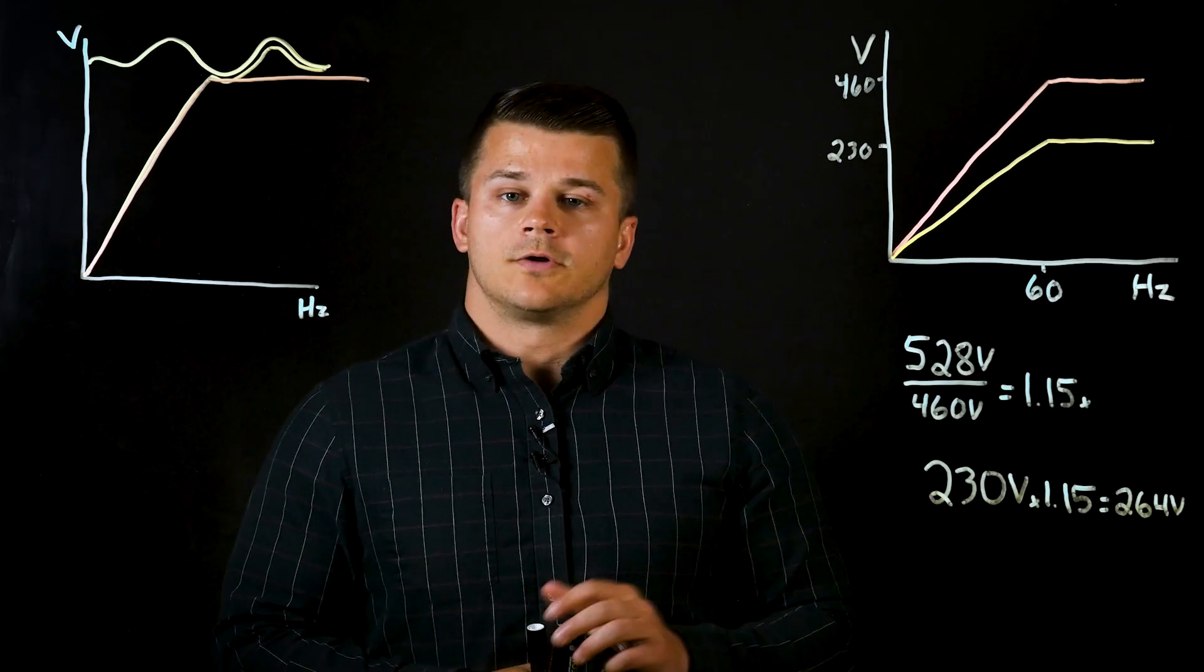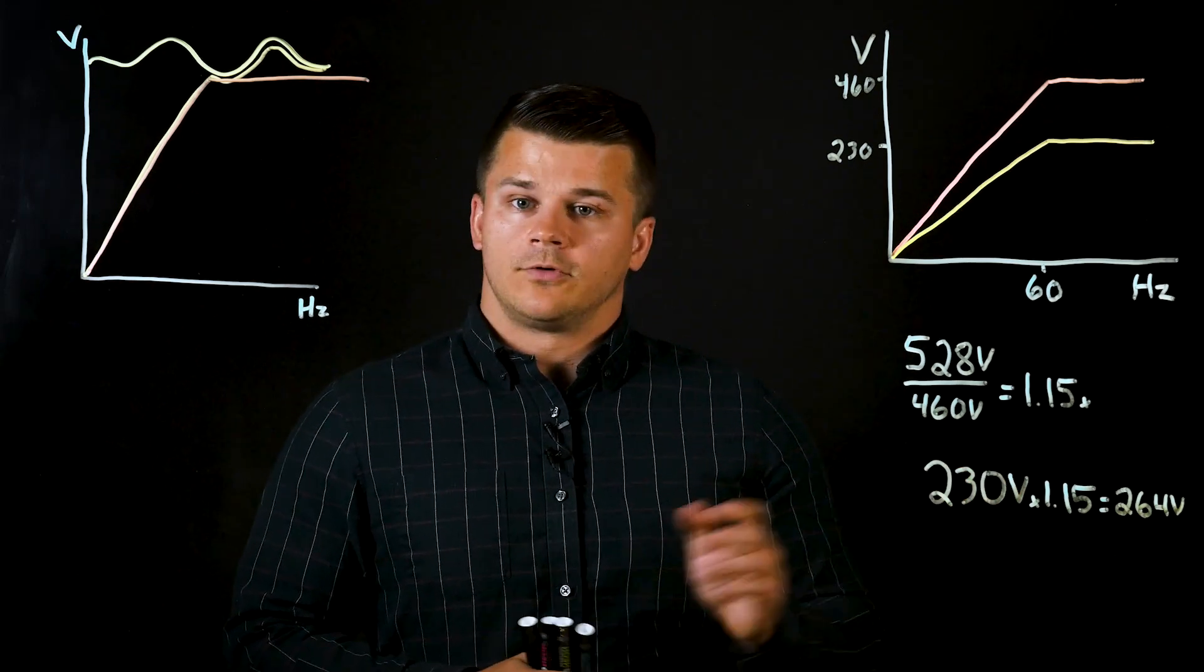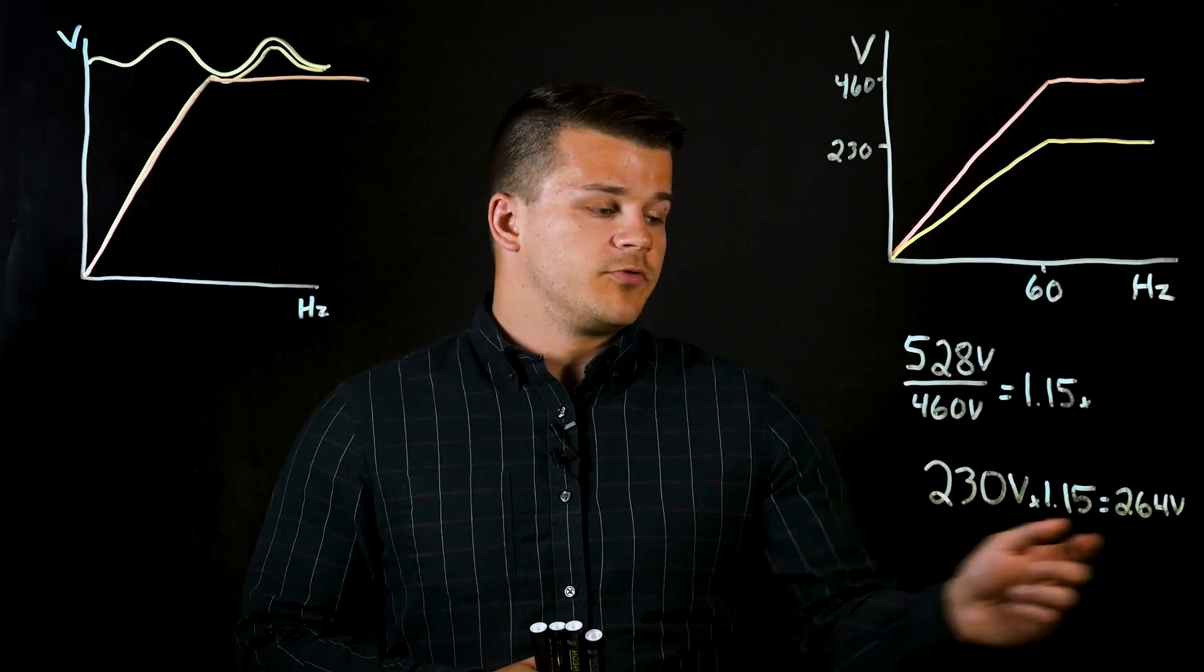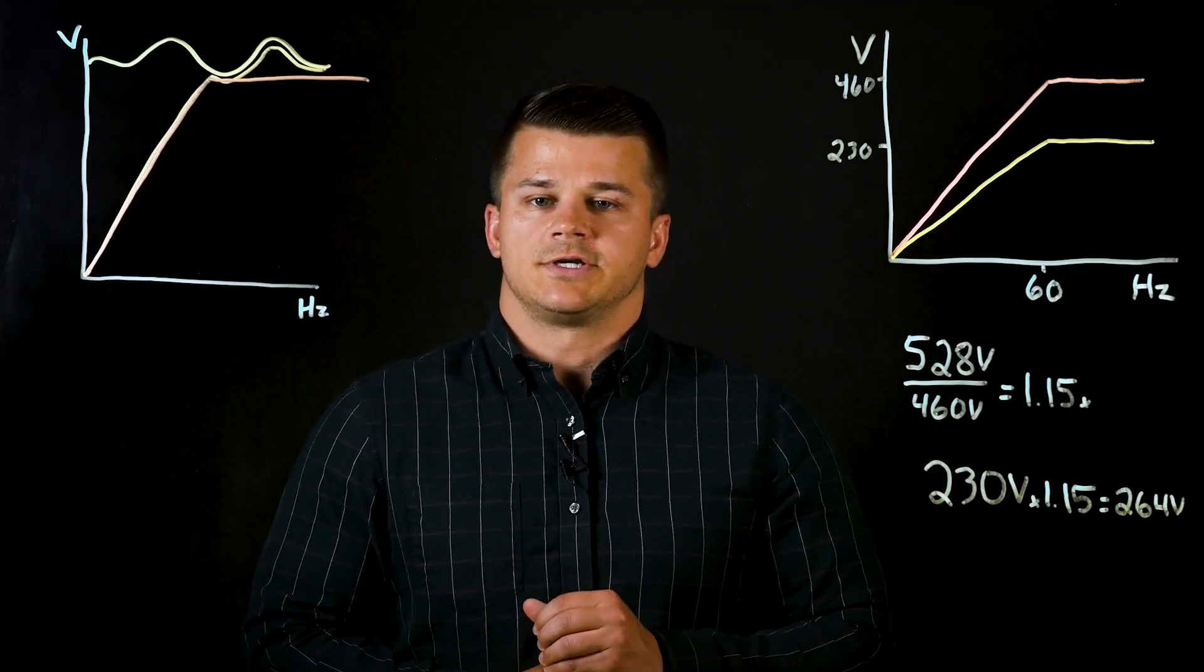For another example with a 230 volt motor, if we take 230 volts, the motor's rated voltage, times this 1.15 factor, we get an output voltage that could be up to 264 volts without the voltage stabilization function.